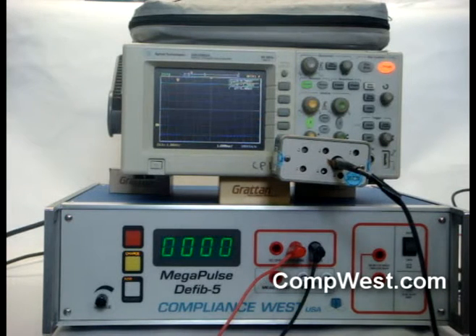We use a Tektronix P6015 1000:1 oscilloscope probe, which has sufficient frequency response to capture the waveform accurately. If you are using a different 1000:1 probe, please be sure it has a frequency response equivalent to the P6015 of 75 MHz minus 3 dB and a minimum voltage rating of 5 kV.